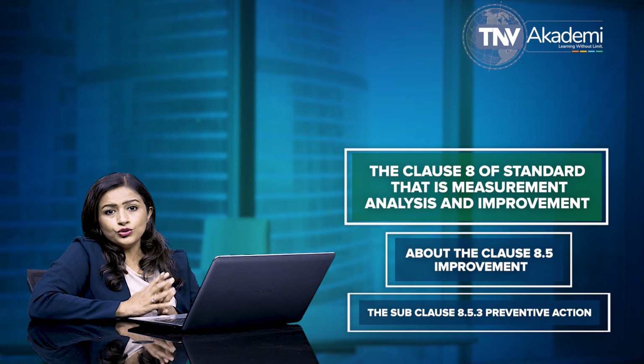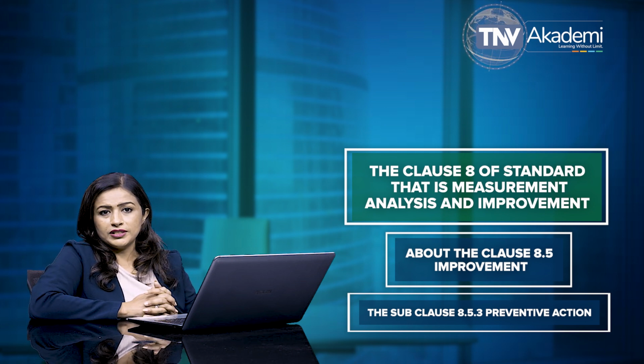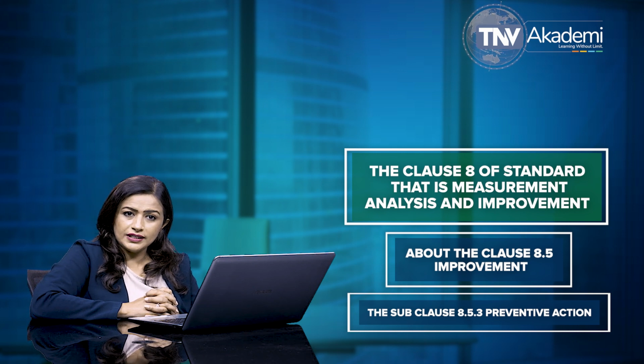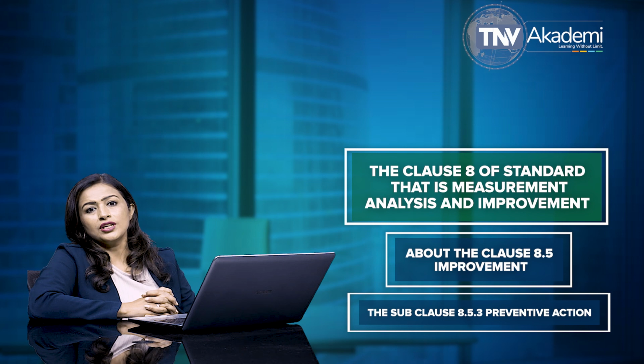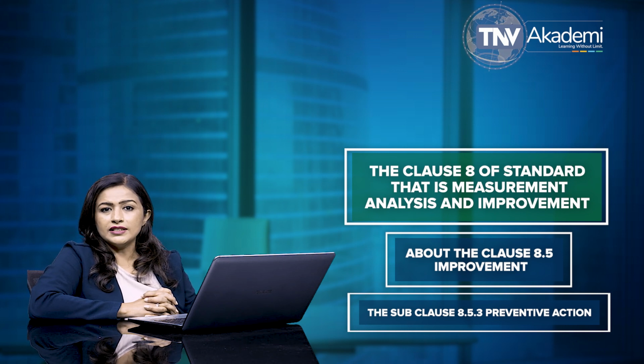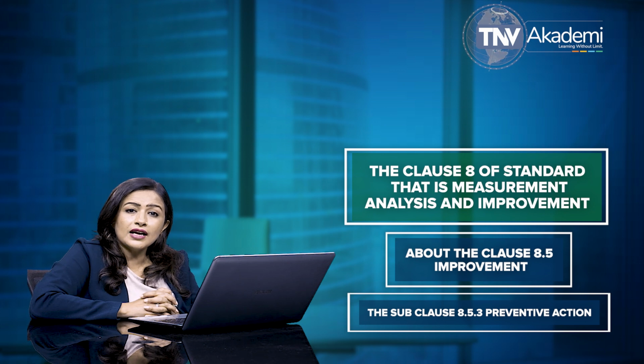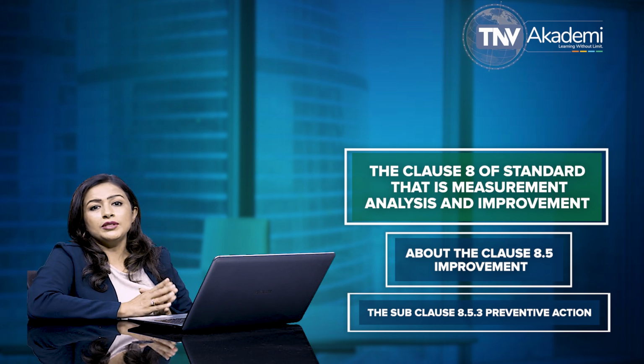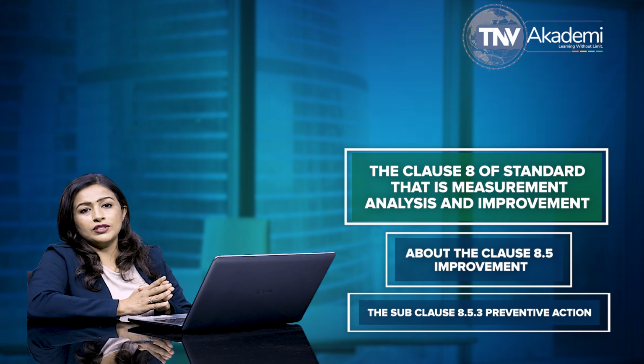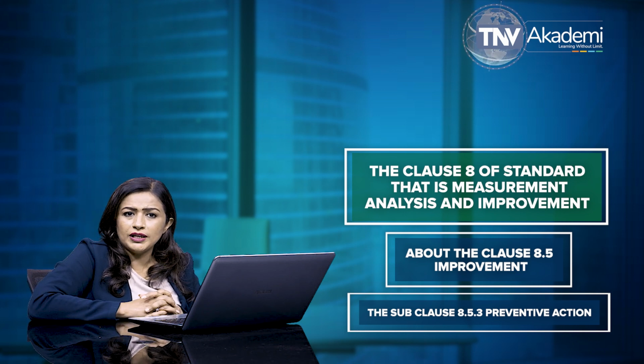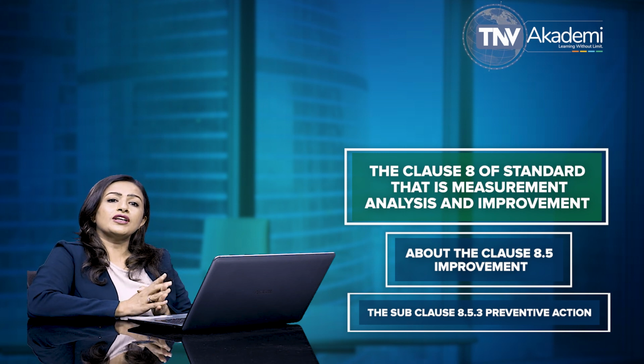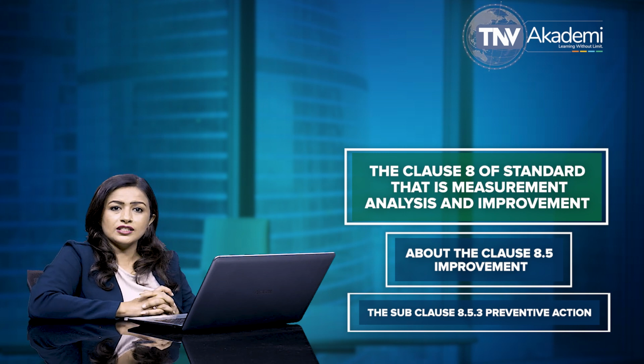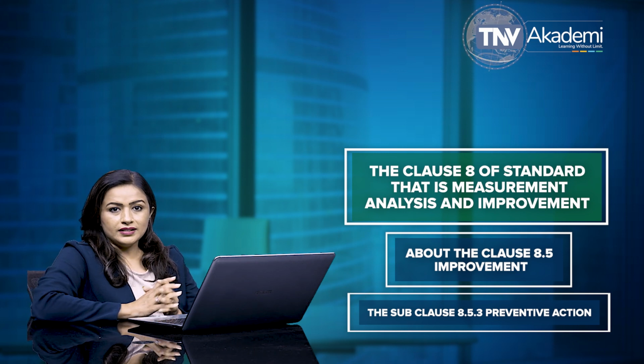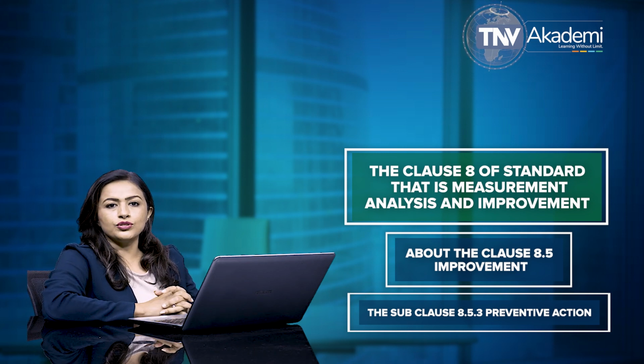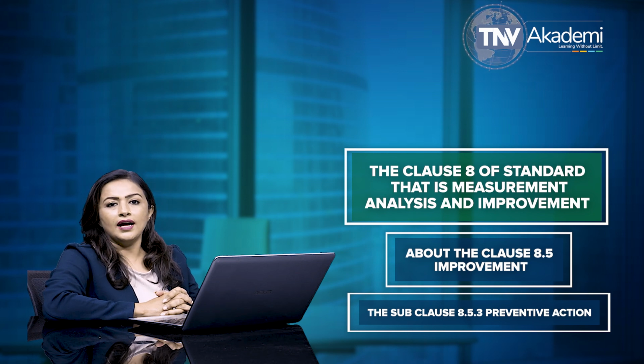evaluating the need for action to prevent occurrence of nonconformities, planning and documenting action needed, and implementing such action, including, as appropriate, updating documentation. Verifying that the action does not adversely affect the ability to meet applicable regulatory requirements or the safety and performance of the medical device, and reviewing the effectiveness of the preventive action taken as appropriate. This clause specifies that the organization must maintain the records of the results of any investigations and of action taken to meet the requirements of the standard.